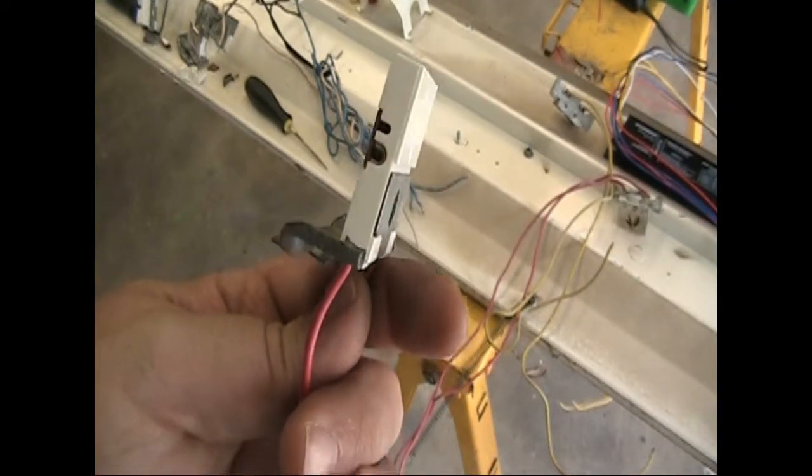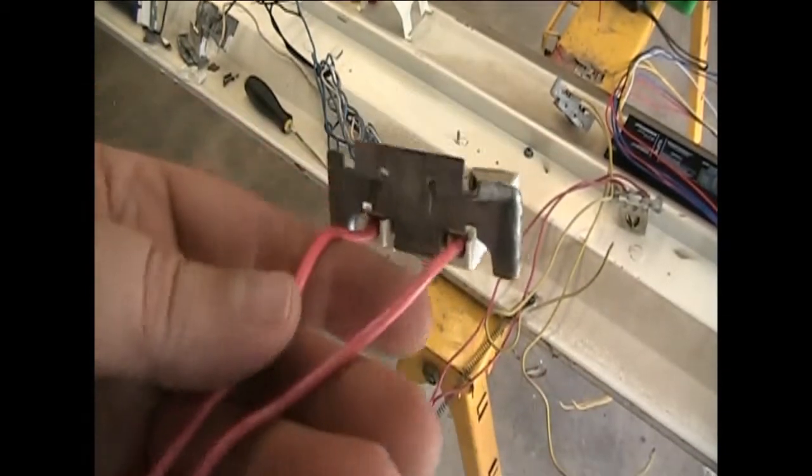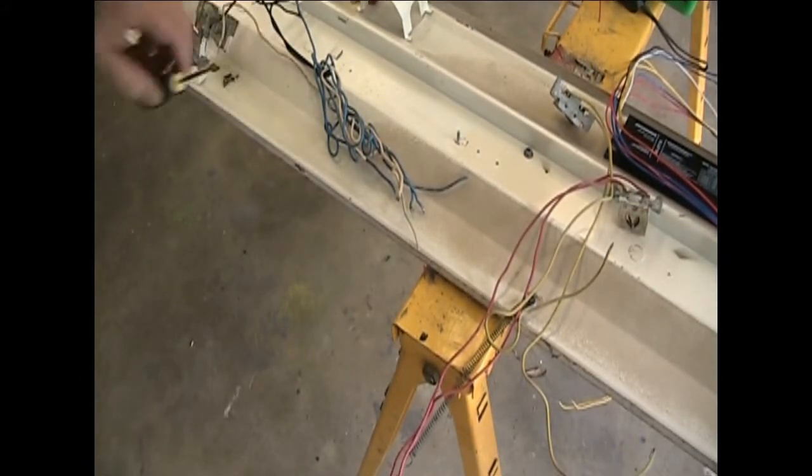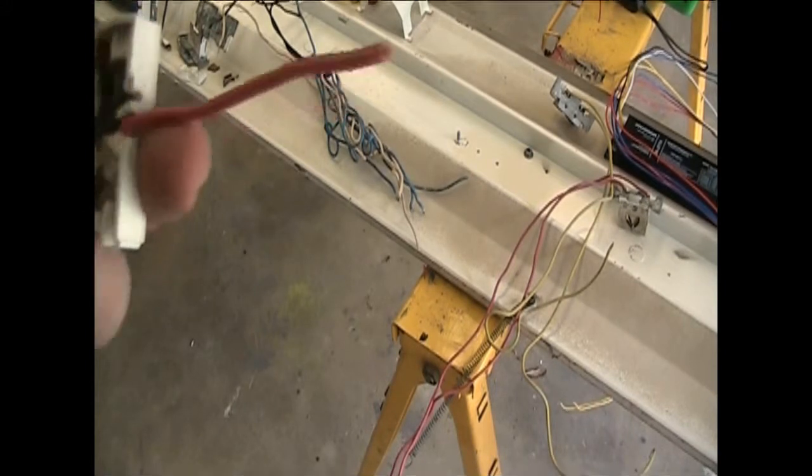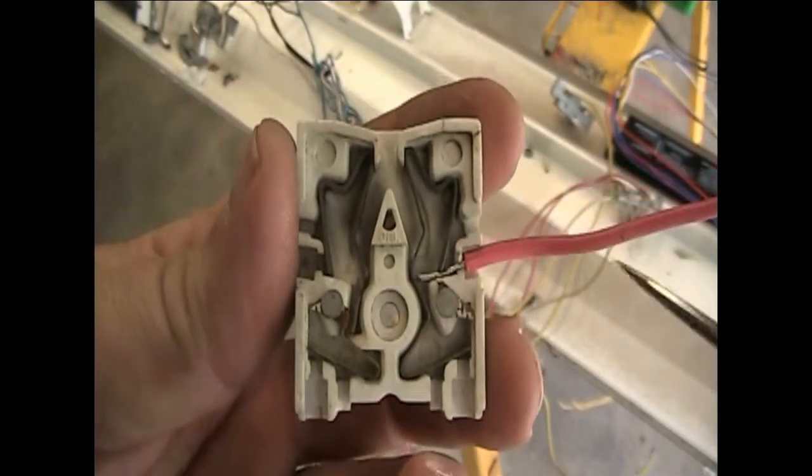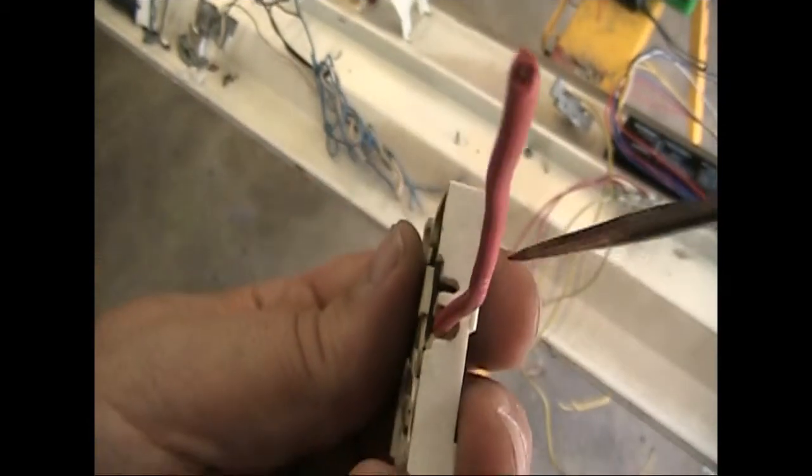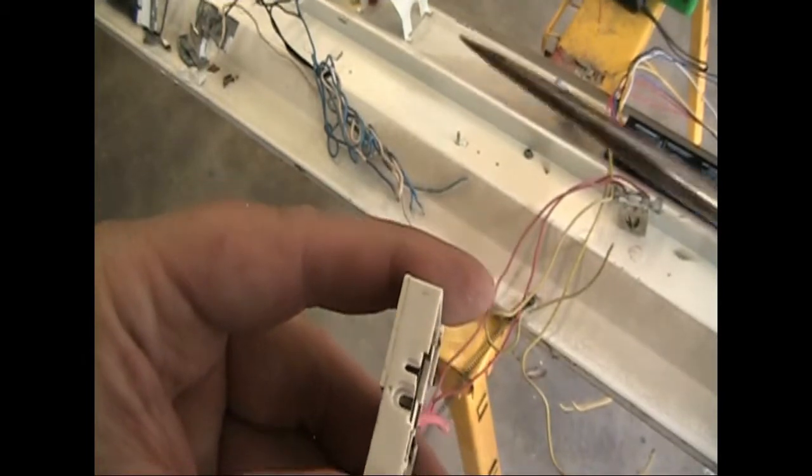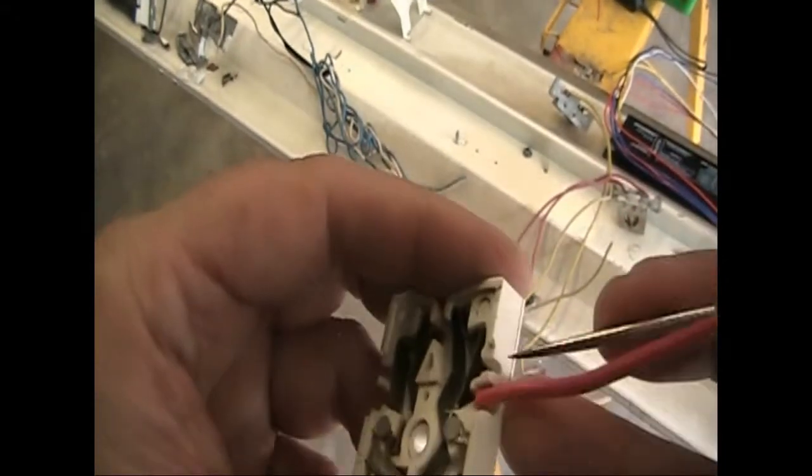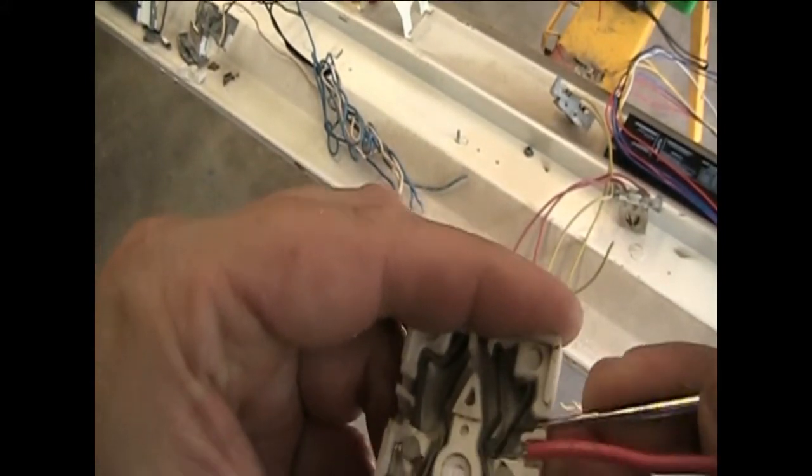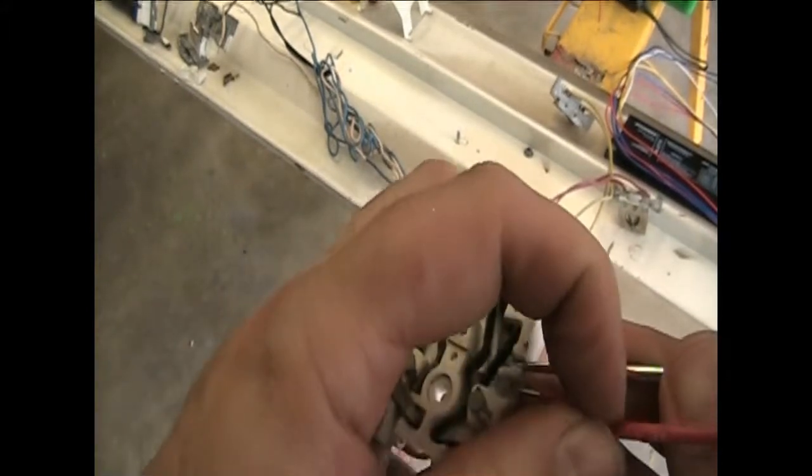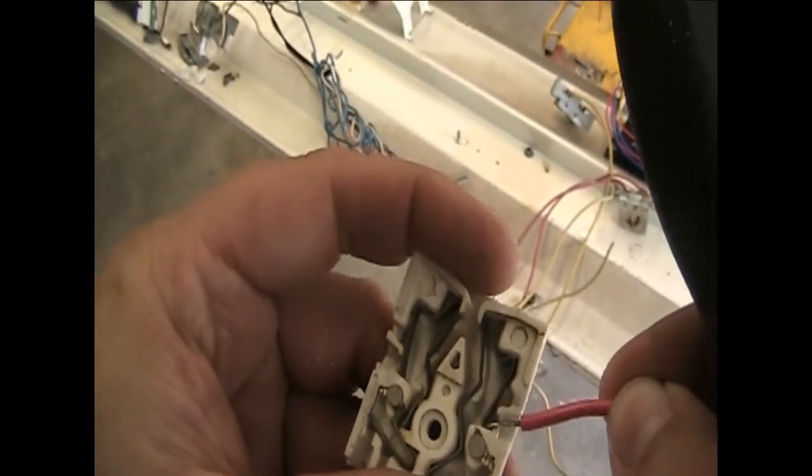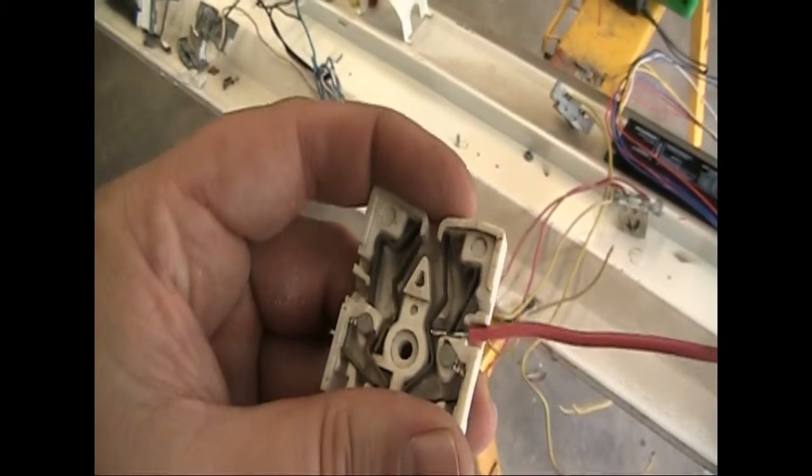Okay, here's a receptacle. This is what they look like. There's the wires going into the unit. Now in order to get the wires out of the unit, I have an open one here. That's how the wires are held in. What you have is slots. There's a big slot which the wire goes in and then there's this slot. What you need is an awl of some sort. What you do is you push it in up against this metal and bend it back. And then the wire slides out just like that. And in order to put it in, later on when we reassemble it, you just push it in like that. And there you go.